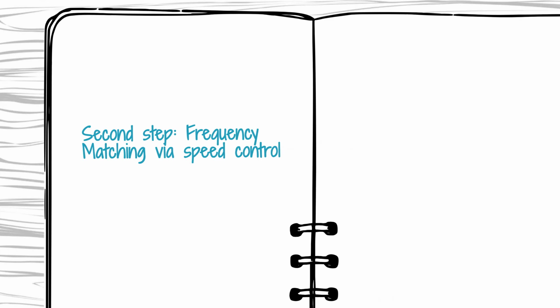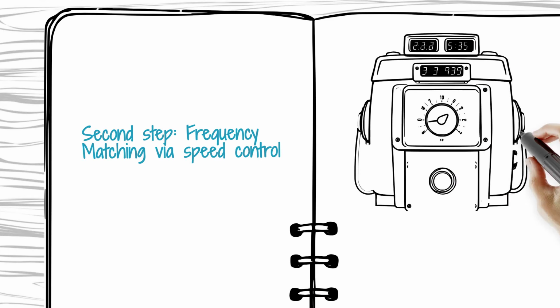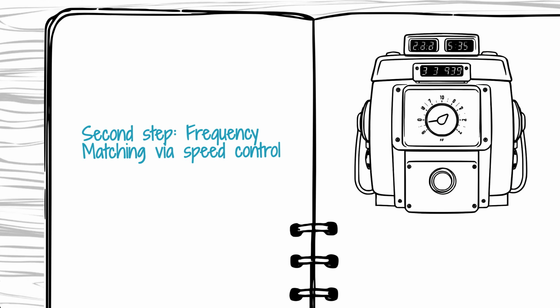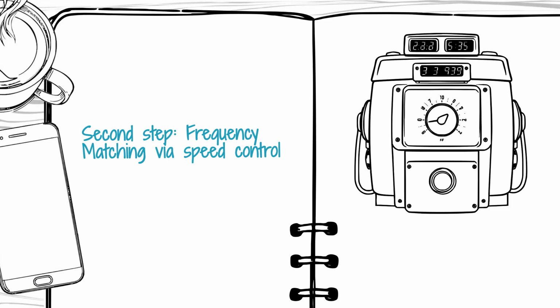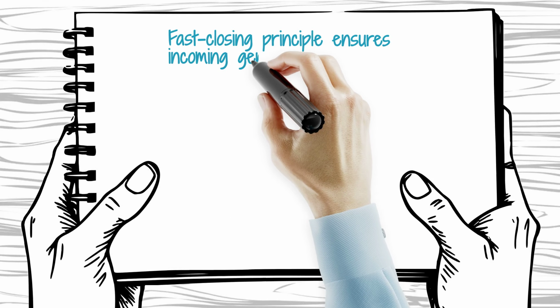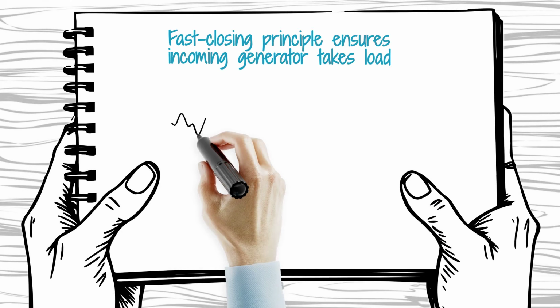Second, frequency matching. Frequency is the speed of the generator tied directly to the engine's RPM. The synchronizer compares the two frequencies and sends corrective signals to the engine's governor control. This electronic or hydraulic governor fine-tunes the engine's speed, bringing the incoming generator's frequency slightly higher than the running frequency. This slight difference is known as the fast closing principle. It guarantees the incoming machine will immediately take a positive real power load upon connection, instead of drawing power.